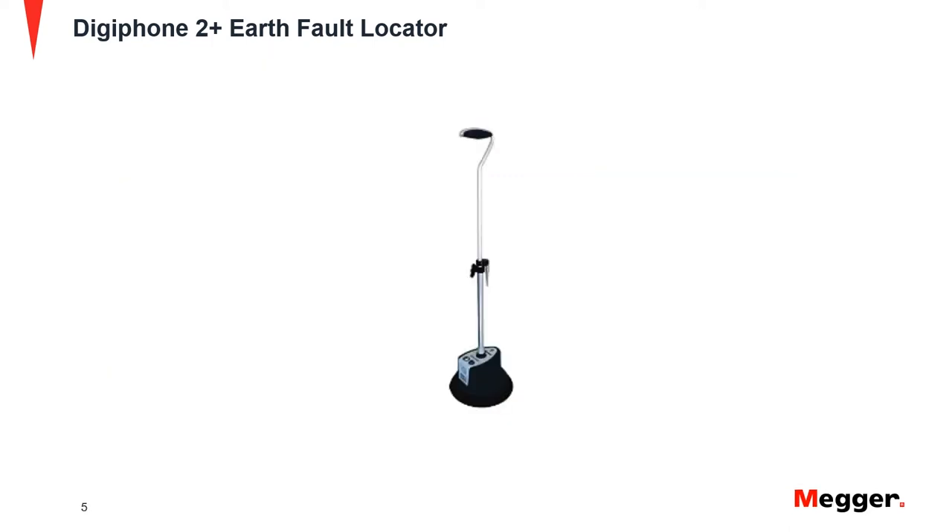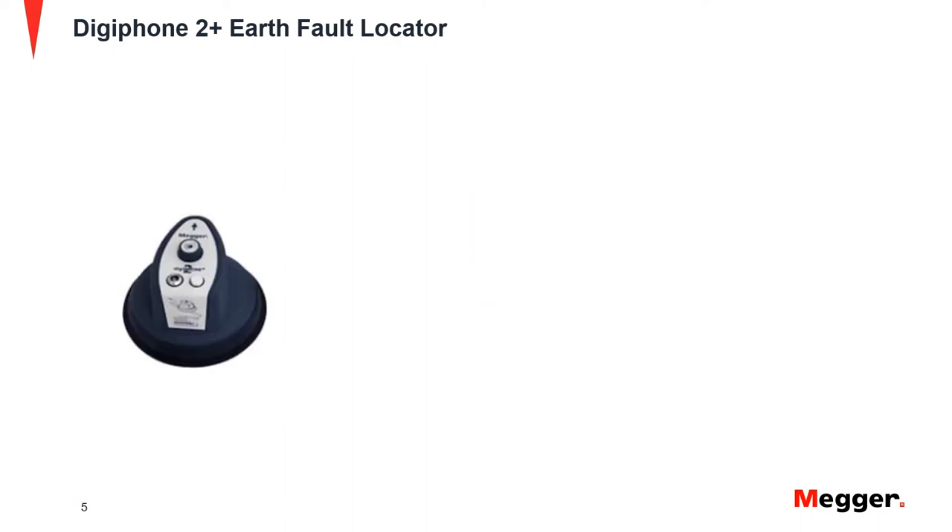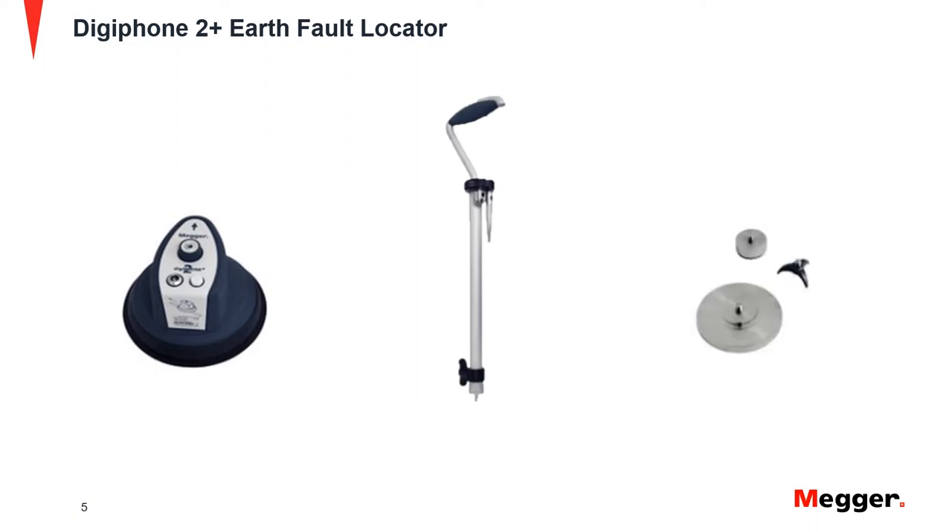This is the Surge Wave Receiver, DPPSU-2, which is used for the accurate pinpointing of faults in buried cables. It is made up of three major components: the DPPSU sensor, the telescopic handle, and different probes that are suitable for different ground conditions.